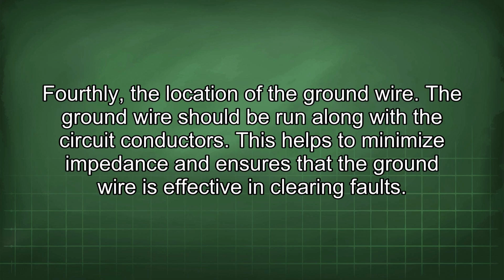Fourthly, the location of the ground wire. The ground wire should be run along with the circuit conductors. This helps to minimize impedance and ensures that the ground wire is effective in clearing faults.